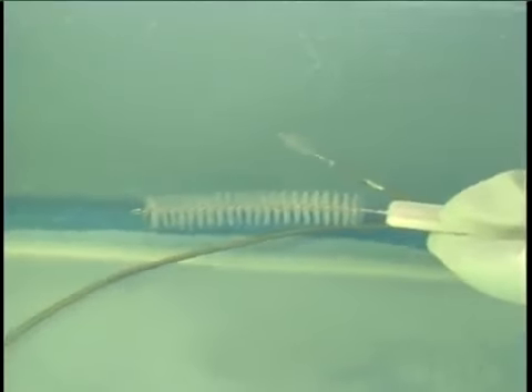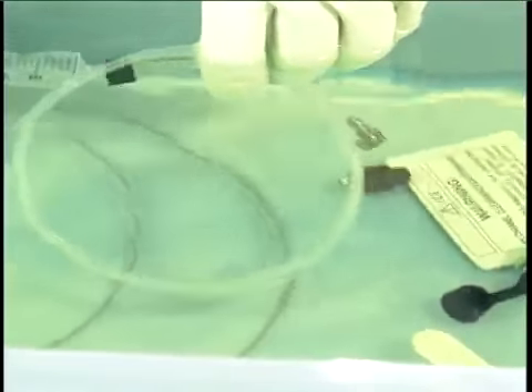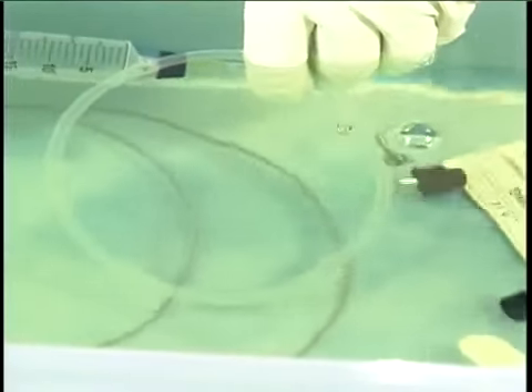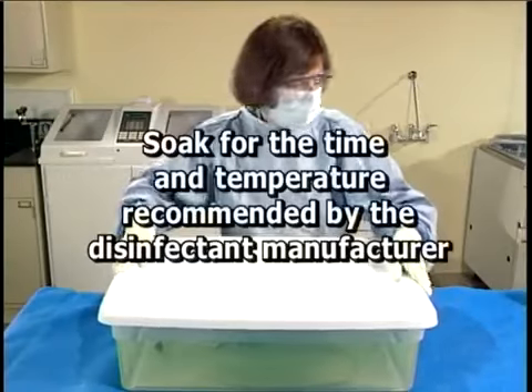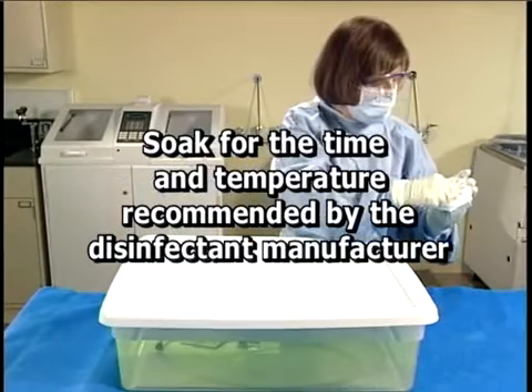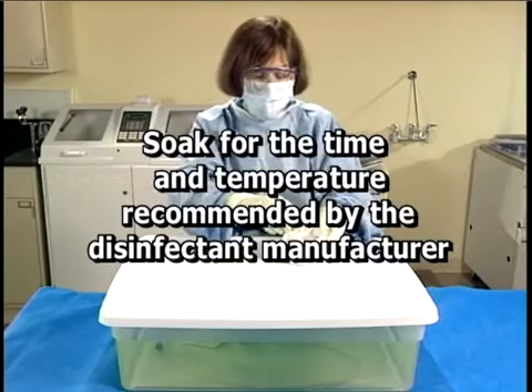Flush the interior and recessed parts of the biopsy valve while immersed. Rub the bristles of all brushes to make sure all air bubbles have been removed. Fill a syringe with disinfectant solution. Attach it to the suction cleaning adapter and flush with disinfectant. After removing the air bubbles from all parts, soak the parts for the specified amount of time and at the temperature recommended by the disinfectant manufacturer.